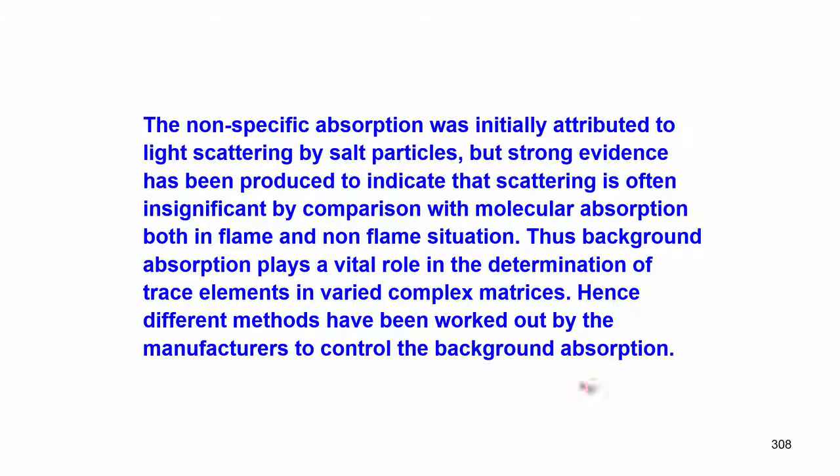The contribution of scattering in atomic absorption is always much less because we take care to keep suspended particles very low. However, if the matrix itself contains solids like sodium chloride in sea water, clogging does occur. It is important to keep the atomic absorption burner clean using a metal blade to keep the holes clear — just like cleaning an LPG gas burner at home. Different methods have been worked out by manufacturers to control background absorption.